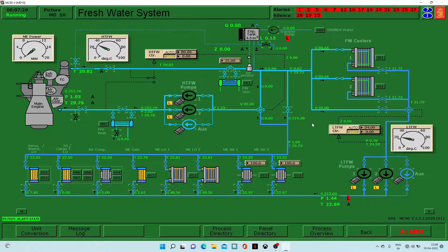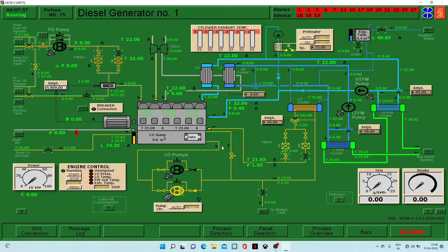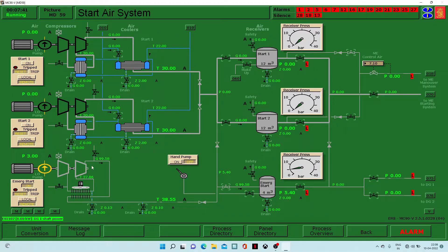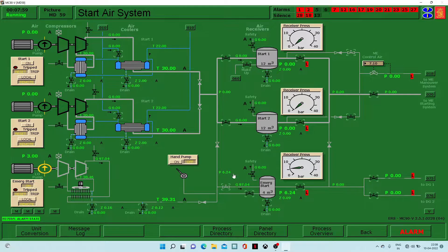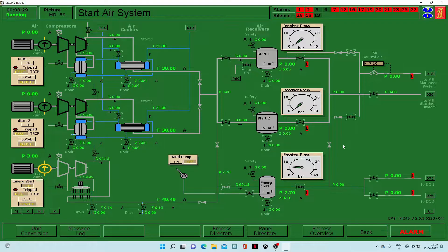All parameters are on the mark and our diesel generator is ready to start. But first, let's check the starting air system — the pressure is 5.57 bar. We have to wait till 10 bar; only after 10 bar can we open the discharge valve going to diesel generator 1 and diesel generator 2. To recap: we have turned on the lube oil pump, maintained lube oil level in the sump, opened valves to the filters, opened the quick closing valve and non-return valve from the service oil tank, turned on sea water supply, fresh water supply, and the emergency compressor for starting air.